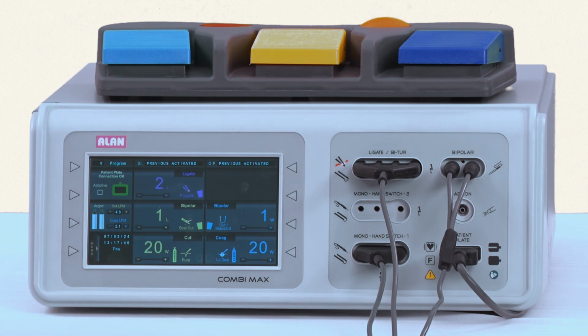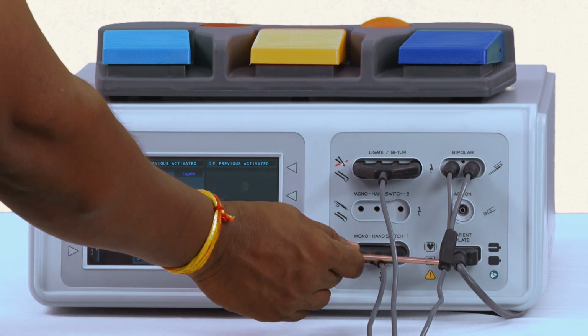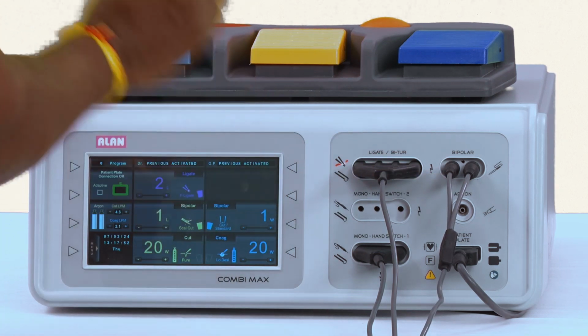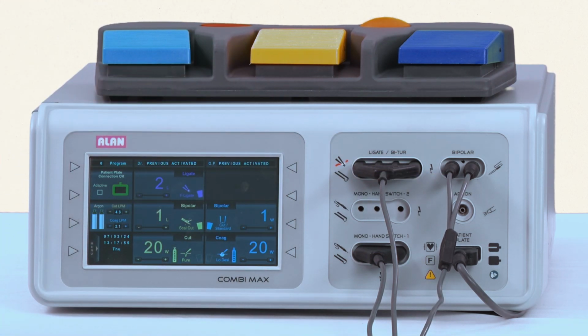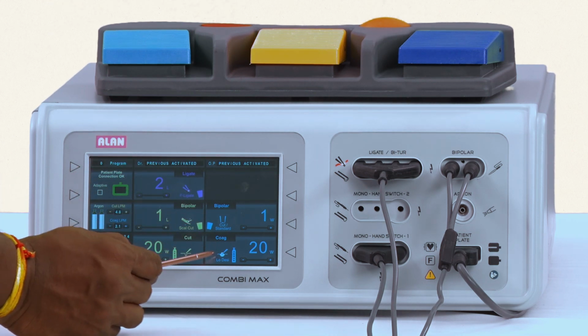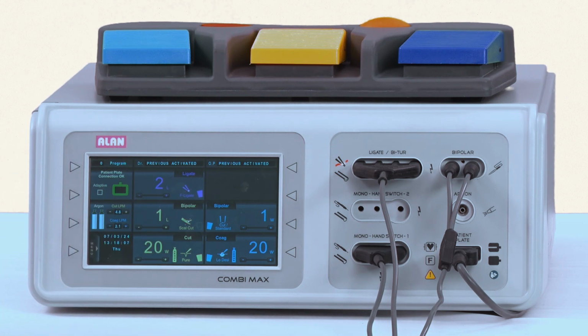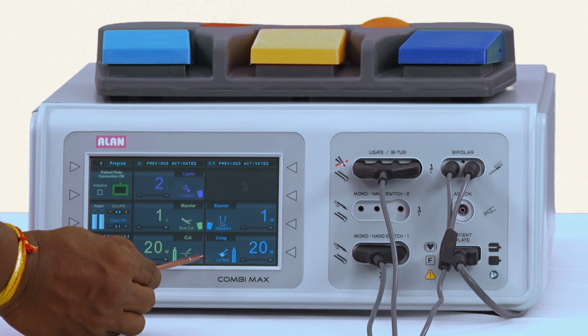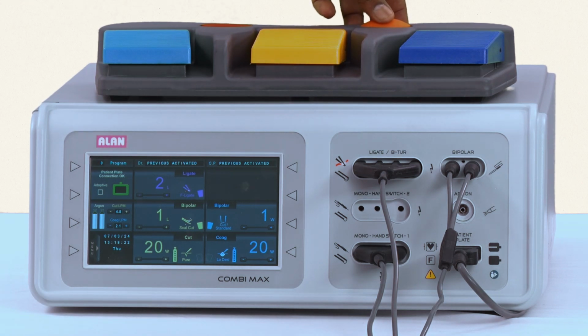We have attached the instruments accordingly for monopolar based surgeries, for bipolar and for vessel sealing. Make sure the foot switch is selected appropriately. Let's assume you want to perform monopolar surgery, then this foot switch should be selected here. If you want to perform bipolar based surgeries, then the foot switch should be selected in row number 2. Now you can do that by pressing on the screen or by toggling between them using the foot switch by pressing this orange button.